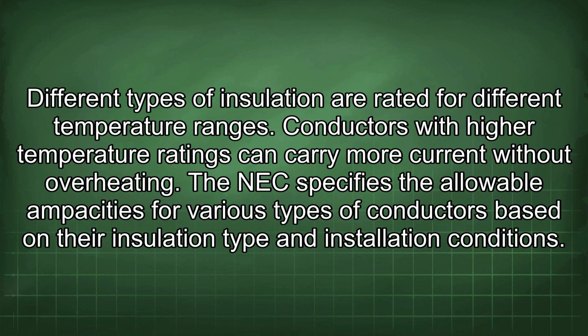Different types of insulation are rated for different temperature ranges. Conductors with higher temperature ratings can carry more current without overheating. The NEC specifies the allowable ampacities for various types of conductors based on their insulation type and installation conditions.